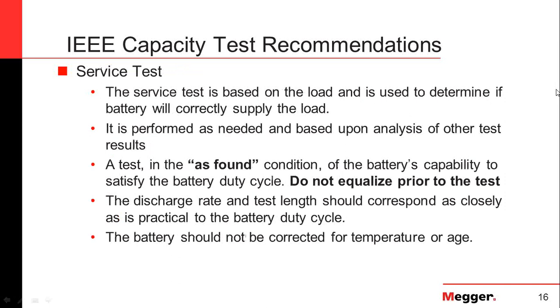The service test is based on the battery's ability to meet its load — what it was designed to carry for the amount of time it was designed to carry. You're testing exactly to those specifications. One key difference: this test is done in an as-found condition, so we do not equalize the batteries prior to the test. Additionally, you will not correct for temperature or age. It's completely in an as-found condition.